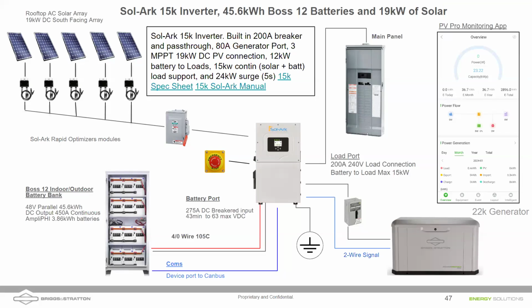Yeah, exactly. And we're looking at a pretty big battery bank here. This is our Boss 12 cabinet. So if you do have it, you want to put our communicating AmpliPHI batteries outside—this cabinet is a NEMA 3R rated enclosure, a nice way to do that. Now, of course, if you're in a cold environment, you might not want to put those batteries outdoors, and you wouldn't necessarily need to purchase an enclosure like this.